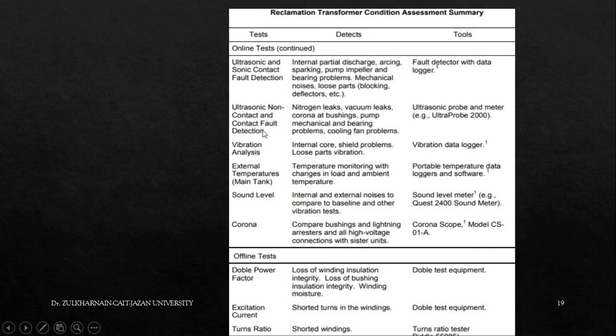Similarly, you have ultrasonic test. You can check for nitrogen leakage. You have learned now how nitrogen is useful, and the leaking of the nitrogen can also be checked. Vacuum leaking can be checked. Similarly, vibration, if at all there in the transformer or in the winding of the motors, can be checked with loose parts. You can tighten and so forth. And there are devices like vibration data logger to check for this.